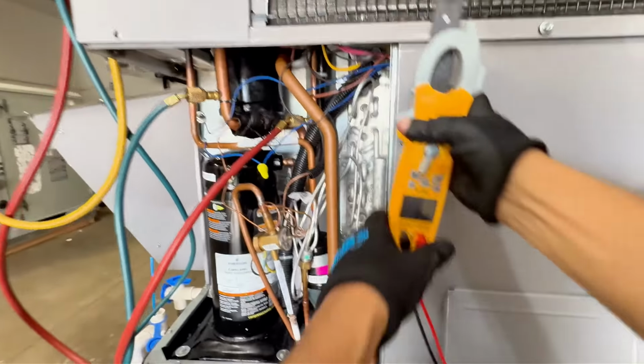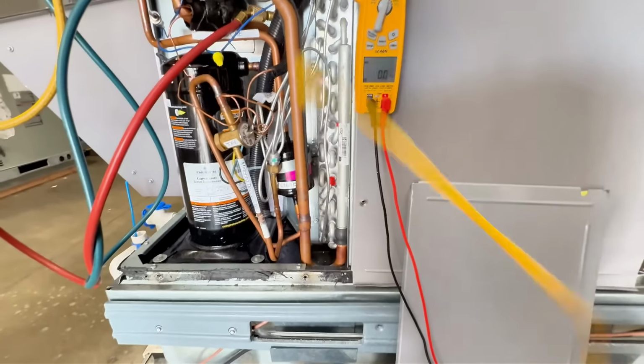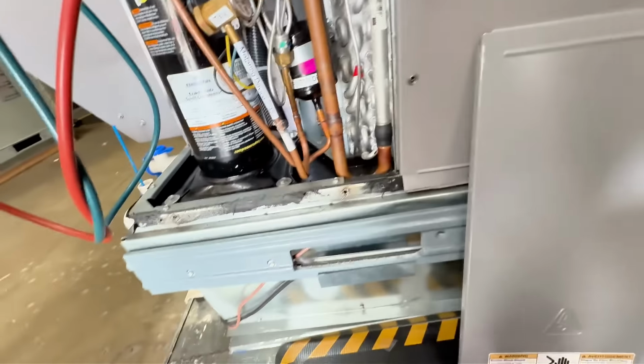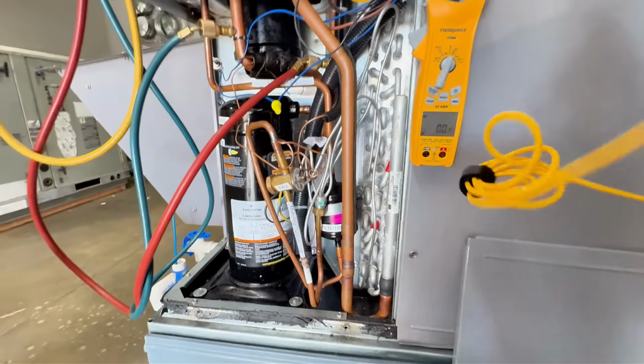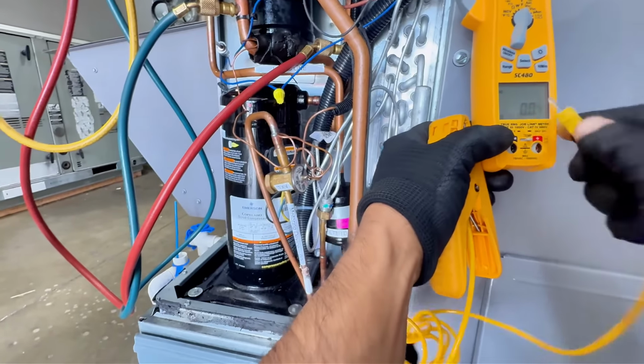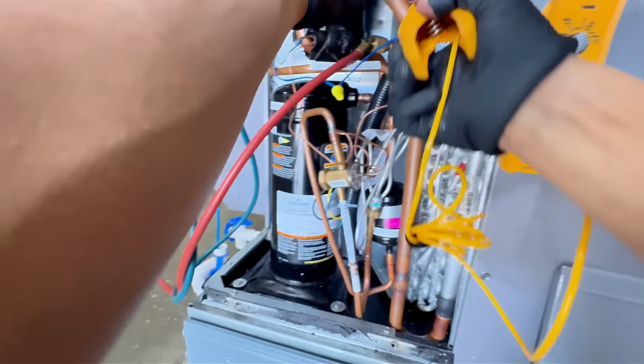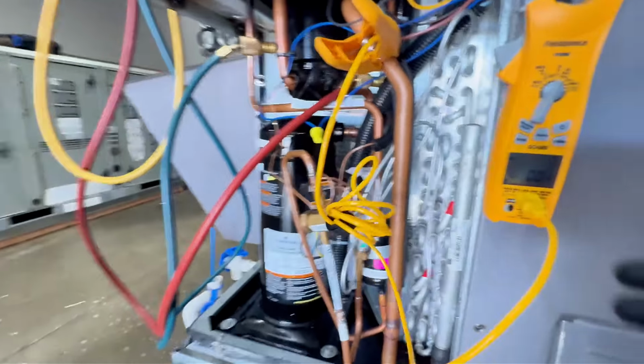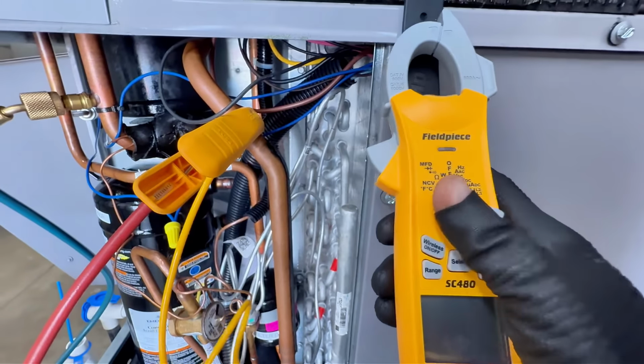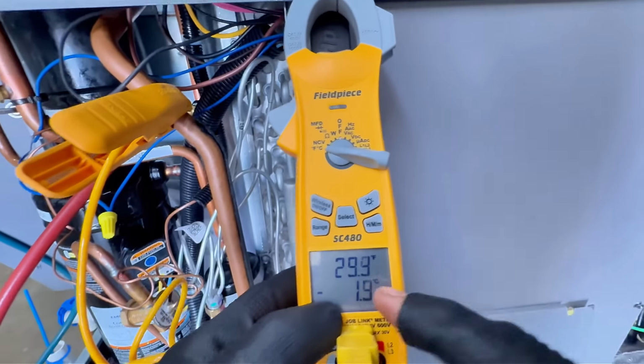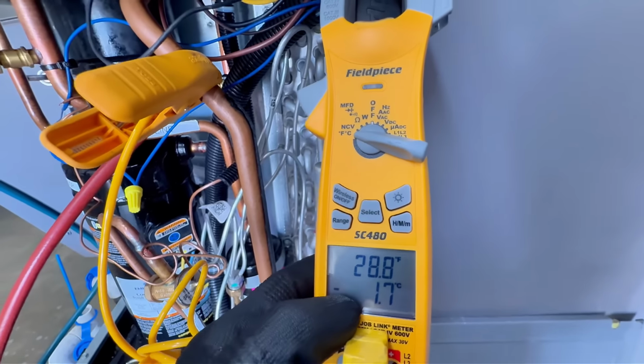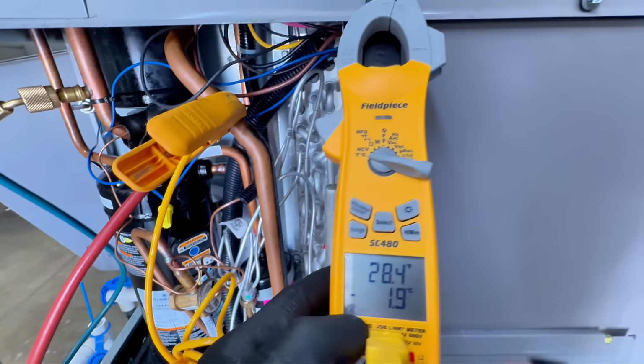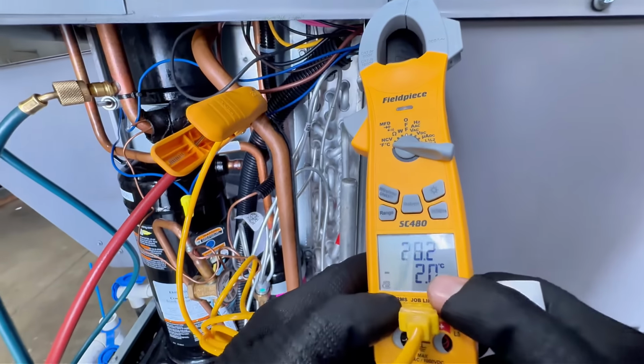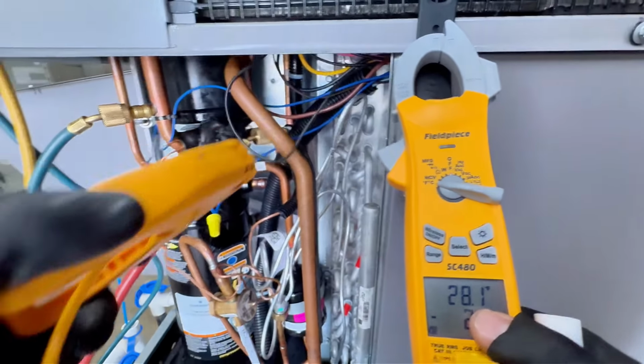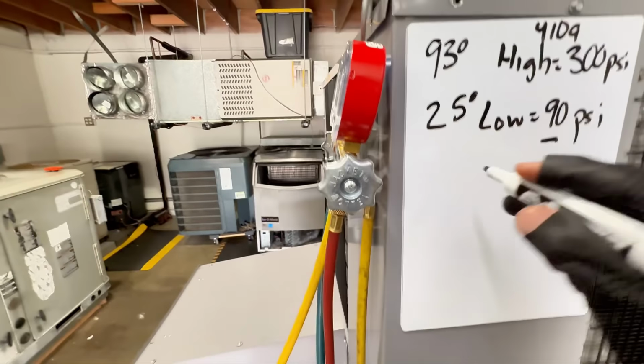Now, remember what I said. You don't need digital gauges, at least. You can just use one of these here, a temperature clamp, and as long as it has a connection to connect your temperature clamps, go ahead and connect it. I'm going to get my suction line temperature first, okay? Suction line temperature first, and then go ahead and put it on Fahrenheit. So right now I'm at, let's see, 28 degrees. Then I'm going to put it over here on the liquid line. We're going to let it change right now.